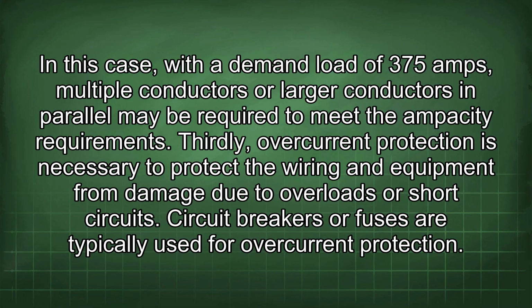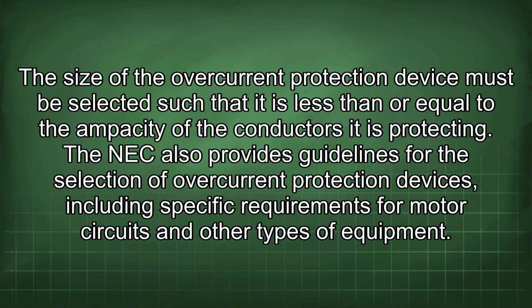Thirdly, overcurrent protection is necessary to protect the wiring and equipment from damage due to overloads or short circuits. Circuit breakers or fuses are typically used for overcurrent protection. The size of the overcurrent protection device must be selected such that it is less than or equal to the ampacity of the conductors it is protecting. The NEC also provides guidelines for the selection of overcurrent protection devices, including specific requirements for motor circuits and other types of equipment.